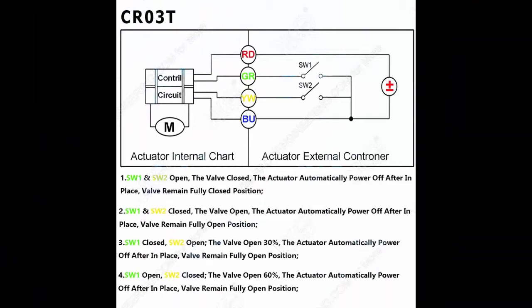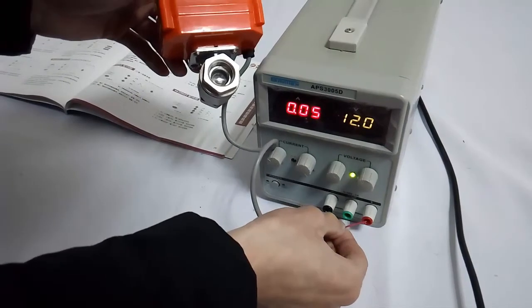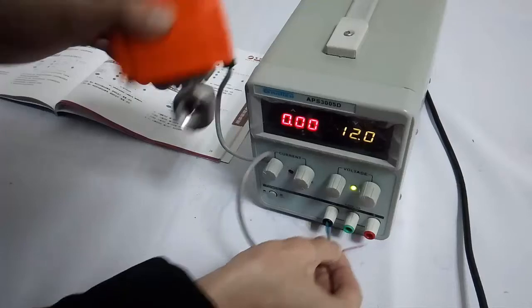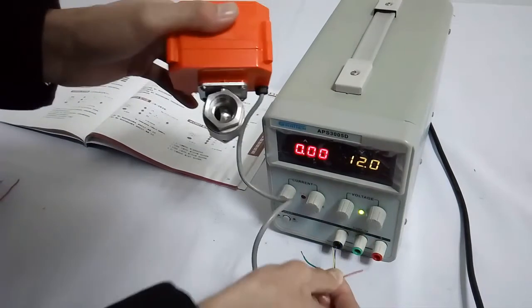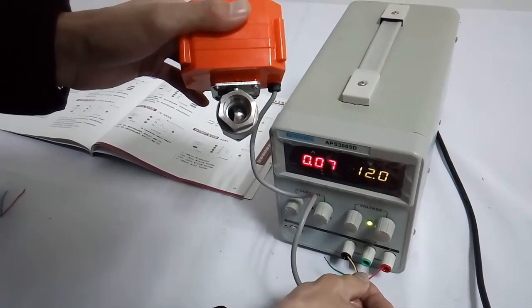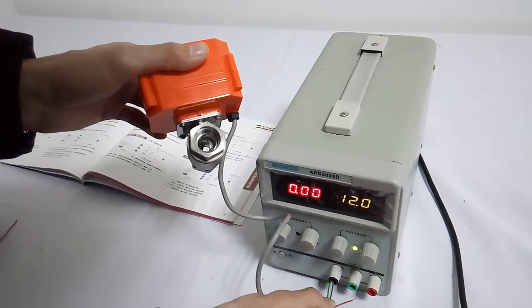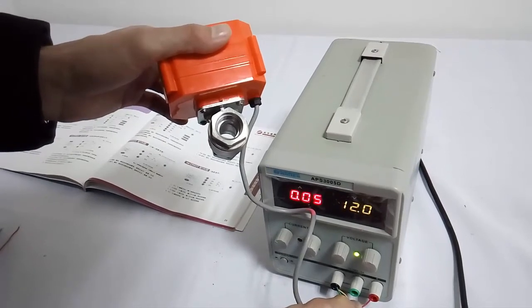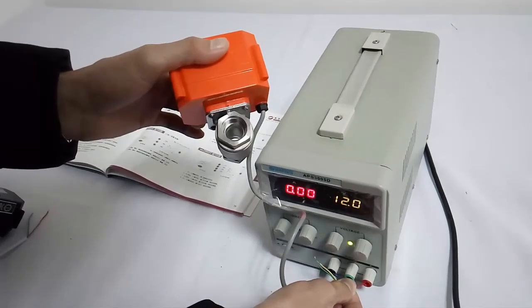Wiring diagram CR03T: It has 4 wires — red, green, yellow, and blue. The red should always be connected to the positive pole. When green and blue are connected to the negative pole together, the valve will be opened only 30%. When yellow and blue are connected to the negative pole together, the valve will be opened only 60%. When green, yellow, and blue are all connected together to the negative pole, the valve will be opened fully. When blue alone is connected to the negative pole, the valve will be closed fully.